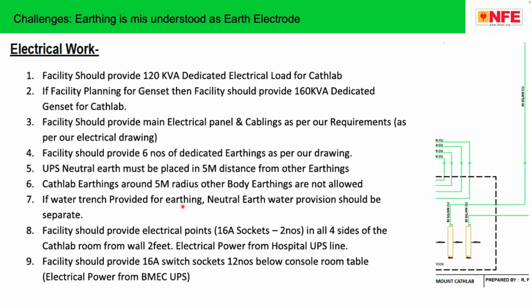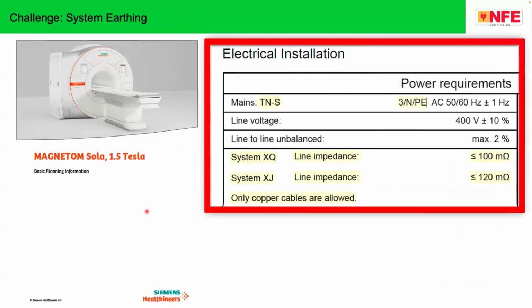If a water trench is provided for earthing, the neutral earthing water provision should be separate. That means you should bring water for the cath lab from your hospital, and water for the neutral earth electrode should come from another panchayat. You see, these are really, sorry to use the word, idiotic electrical installation practices. These are not at all scientific, and these are the reasons for accidents most of the time.